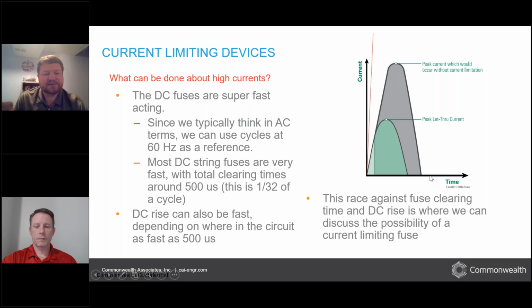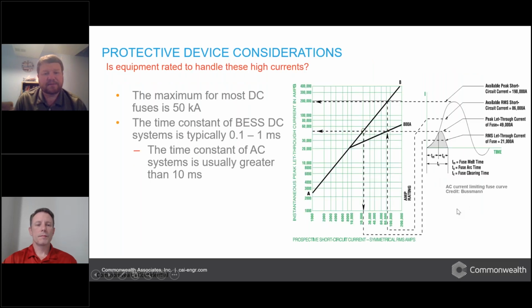You want to flip screens here? Next slide. All right. So when you're working with current limiting fuses in the AC world, because the AC frequency is set and we know what those AC rises are going to look like, and we typically work with a relatively static range of maximum AC fault currents, you have charts like this.